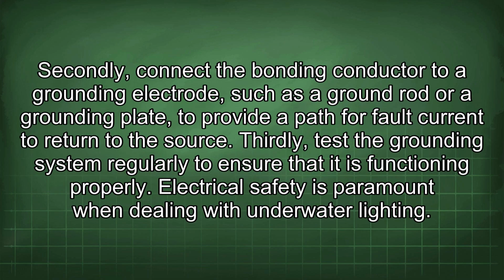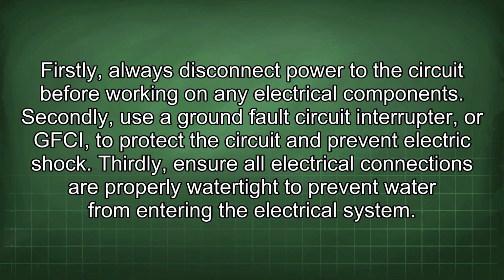Secondly, connect the bonding conductor to a grounding electrode, such as a ground rod or a grounding plate, to provide a path for fault current to return to the source. Thirdly, test the grounding system regularly to ensure that it is functioning properly. Electrical safety is paramount when dealing with underwater lighting. Firstly, always disconnect power to the circuit before working on any electrical components. Secondly, use a ground fault circuit interrupter, or GFCI, to protect the circuit and prevent electric shock.